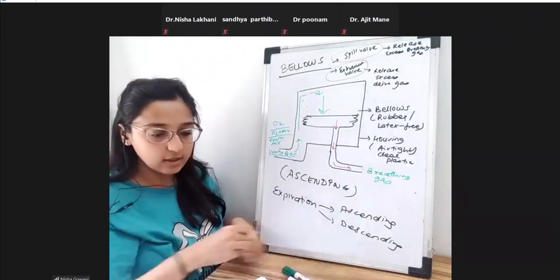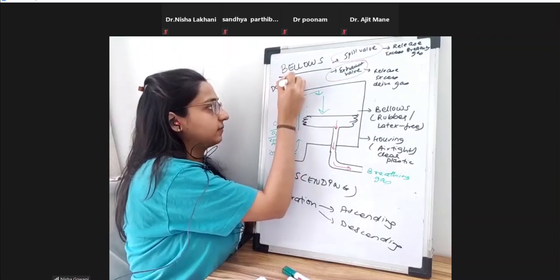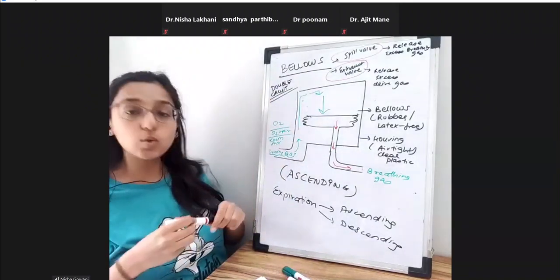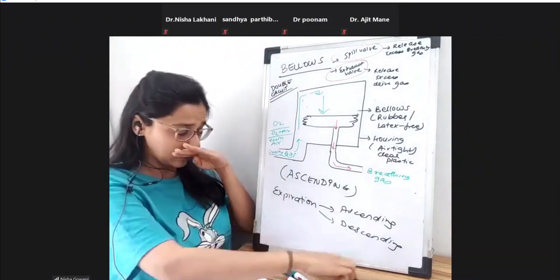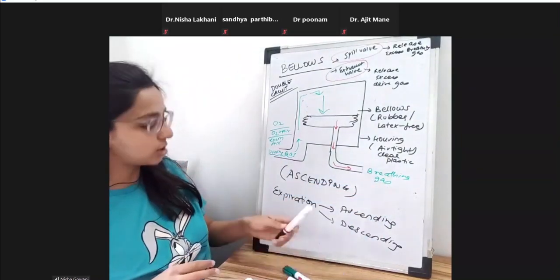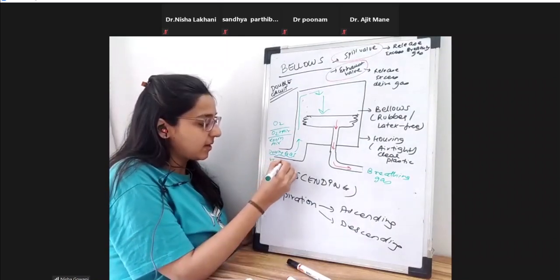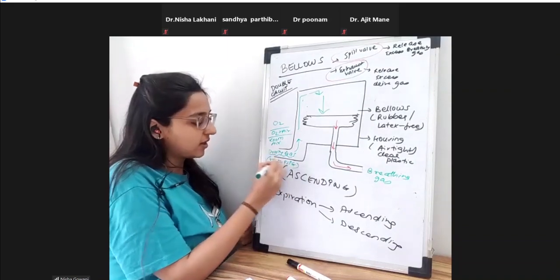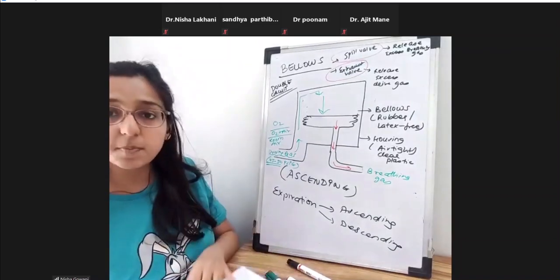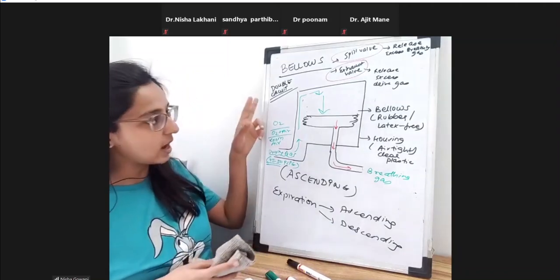The bellows ventilator is also known as the double circuit ventilator. Why is it called double circuit? Because there are two circuits of gases: there is a driving gas circuit and there is a breathing gas circuit — that's why it's called dual circuit. The pressure of the driving gas is 45 to 50 psig (pounds per square inch gauge).